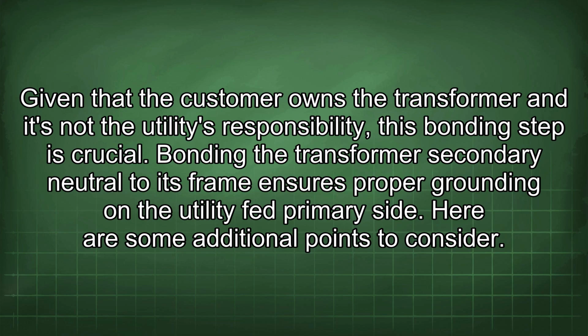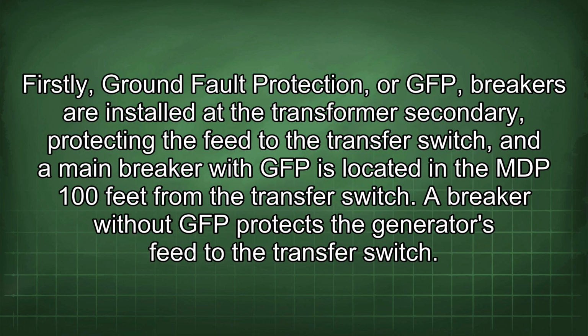Here are some additional points to consider. Firstly, ground fault protection, or GFP, breakers are installed at the transformer secondary, protecting the feed to the transfer switch, and a main breaker with GFP is located in the MDP 100 feet from the transfer switch. A breaker without GFP protects the generator's feed to the transfer switch.